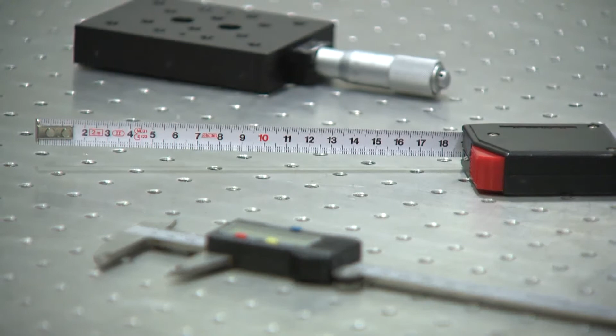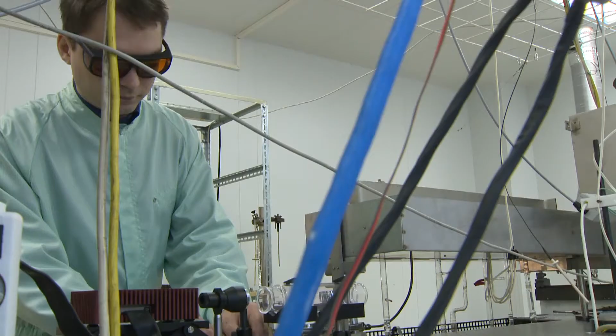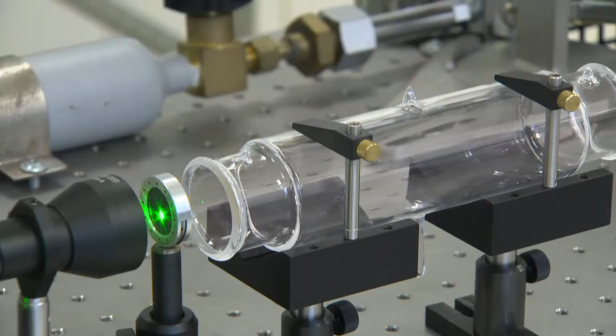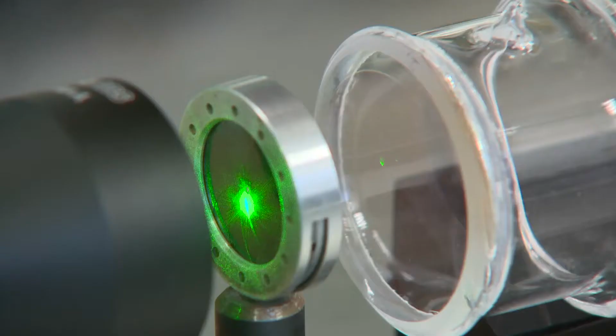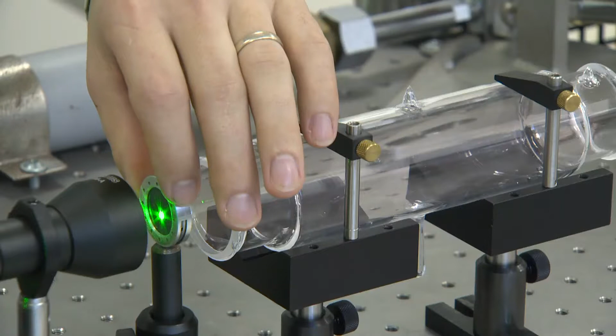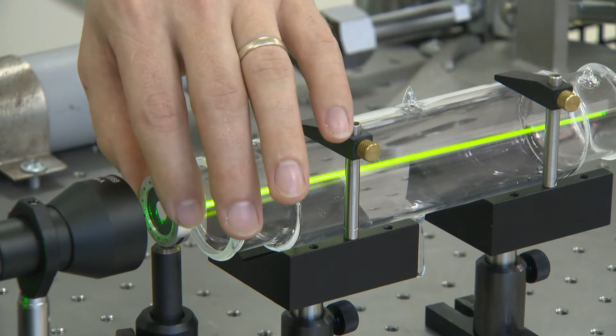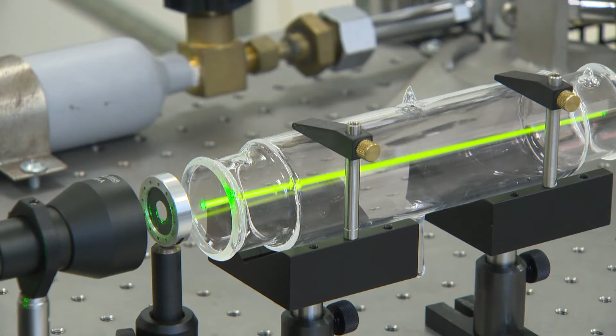We have a wide range of gauges to measure kilometers, meters, millimeters. To make sure that we measure lengths correctly, we calibrate the length measuring instruments regularly. For the most accurate calibration, we use laser light, whose wavelength we know very accurately with an accuracy of many decimal digits. The light allows us to perform length calibration with the resolution down to the size of a single atom.